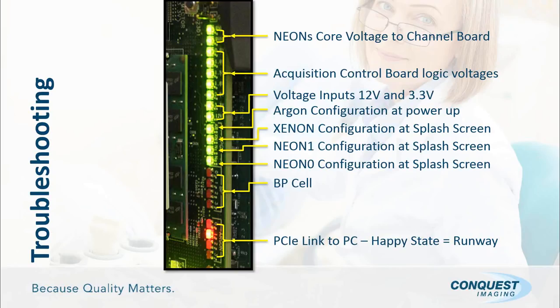Then we go on to the acquisition control board. And this, keep in mind, I'm going to show you a video on the next slide, so you'll see a little bit more how this actually looks in real time. But you have your neon core voltage to channel board. Those are clearly identified at the top. You have your acquisition control board logic voltages. Then you have your 12 and 3.3 voltages that are delivered there, and it'll tell you whether you're getting those. And then you have your argon configuration.